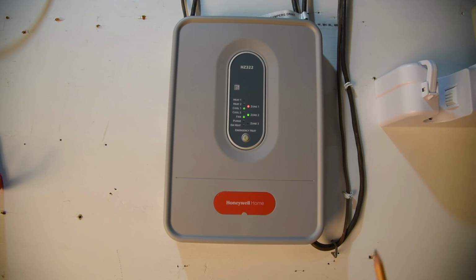What's going to happen now, since zone 1 is not calling for air conditioning and I need air conditioning up on the second floor, zone 2, it's closing the dampers on zone 1. This will place the air conditioning where I want it. Since I don't have a problem with downstairs, it still gets a little bit of air conditioning. I've only blocked off 4 dampers. Remaining dampers still get air conditioning, and one of them gets a little bit of bleed through the way it's set.